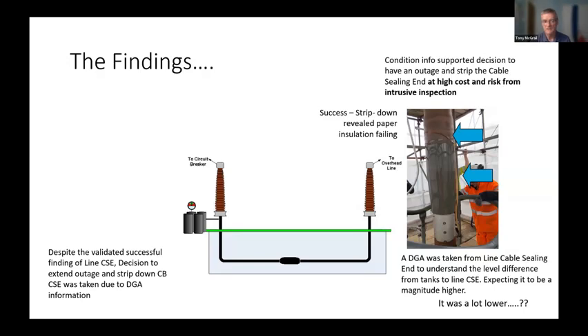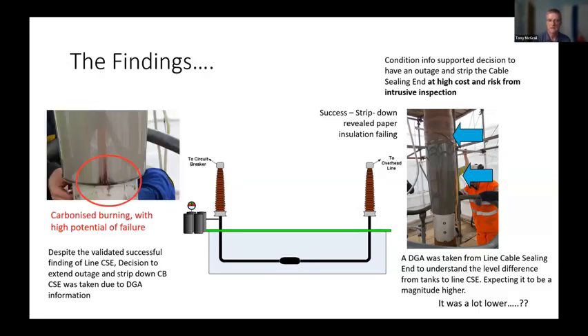And the decision was taken to extend the outage and break down the other cable sealing end and see what we could find. To a degree, there's clutching at straws, but there's also a whole safety aspect of this that we really don't want to put a line back in service where we have high DGA and can't explain it based on the fix that we've put in place. Just pure risk analysis. Next one, please.